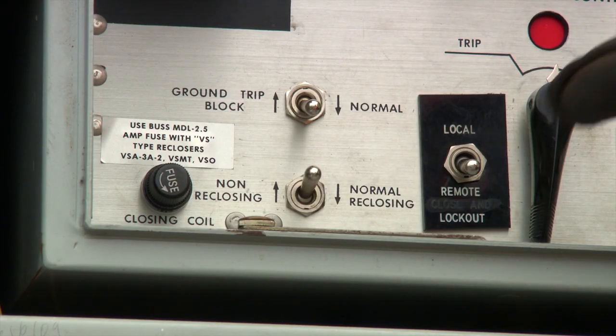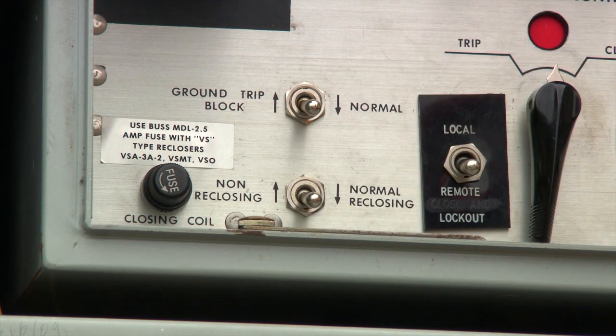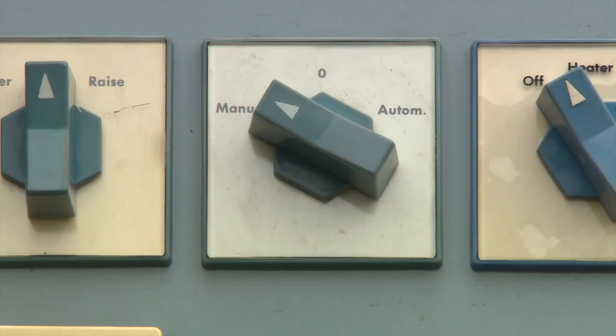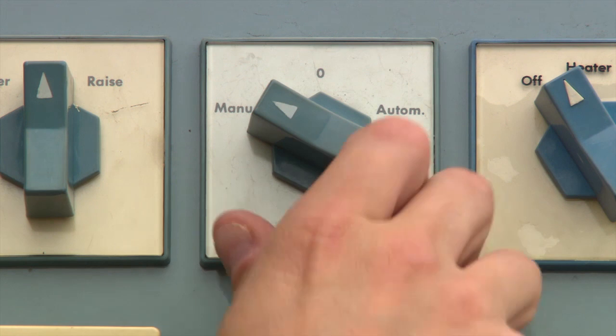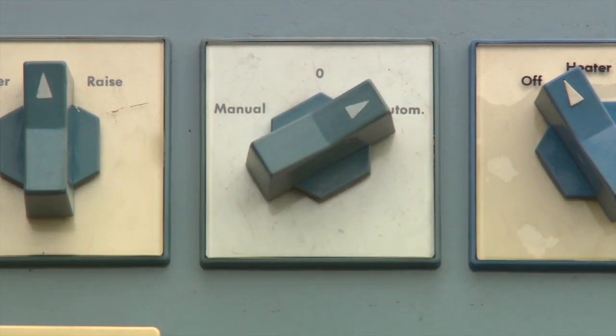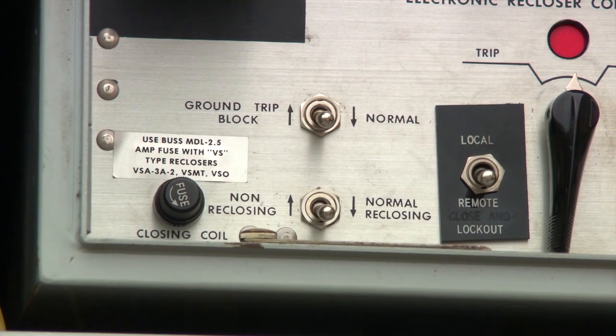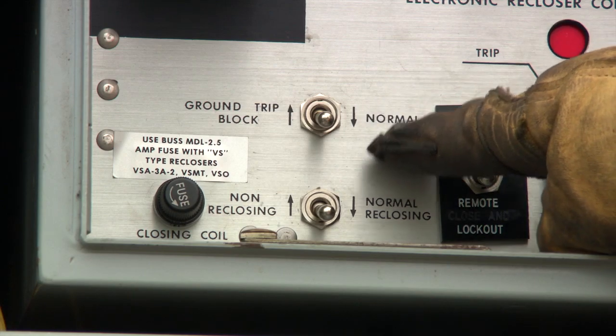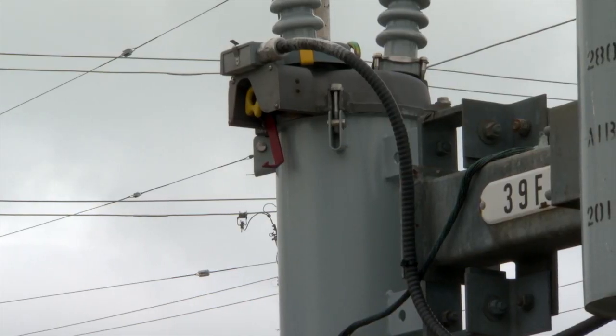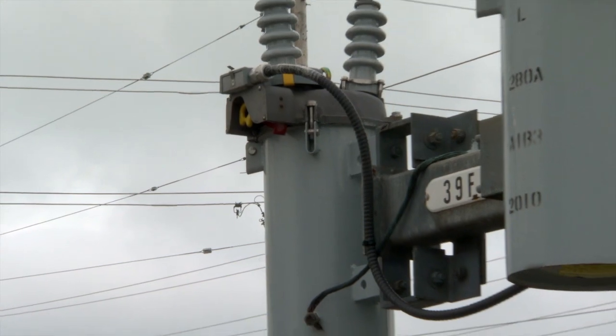Place the MUS F1 non-reclosing normal reclosing switch in the normal reclosing position. Place the MUS ULTC controls in the auto position to regulate station load. The tap changer should not raise or lower more than 2 taps. Check that the MUS F1 ground trip blocking switch is in the normal position. Place the station reclosers into the reclose position to restore normal operation.